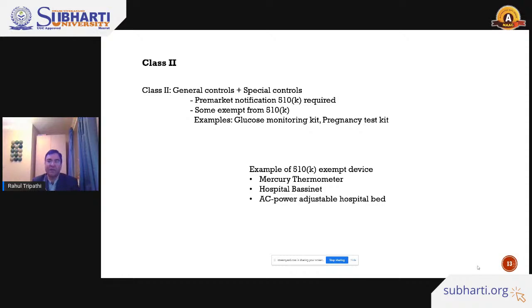But here in class 2, the pre-market notification 510k form is required for every medical device falling under class 2. Some of these medical devices are exempted from the 510k form, like mercury thermometers, hospital bassinets, or AC powered adapters for hospital beds. So hospital bed adapters still sit in class 2, but you can get an exemption from filling out the 510k form. And for class 2, glucose monitoring kits and pregnancy kits are general medical devices falling in the class 2 medical device systems.